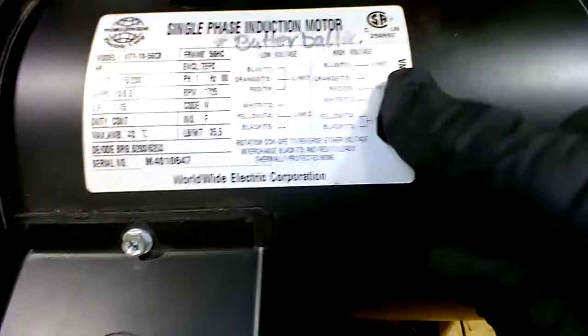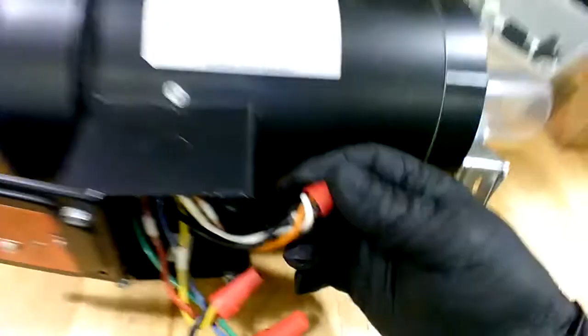And then the insulated bundle, instead of it being orange, red, white, it should be orange, black, white, because we reversed the black and the red. So orange, black, white should be in there for the high voltage, and that's correct. Those colors are the ones internal in the motor, not the incoming white wire or black, but the winding wires that are within the motor.